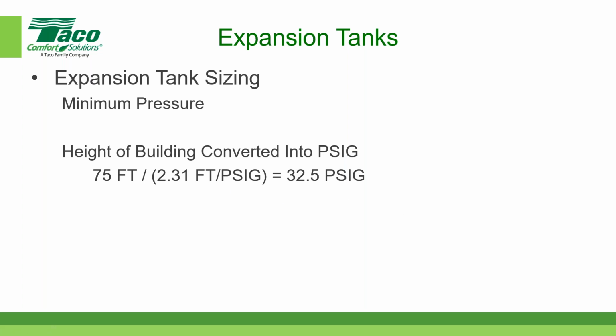The assumption here is that not only is our building 75 feet tall, but the piping system goes from the lowest part of the building to the highest part of the building. So if we want to determine what the pressure is at the bottom of the building, which in our case just happens to be where the expansion tank is located, then you would take that height and divide by 2.31 to convert that into 32.5 pounds per square inch gauge. So that's where you get the initial static pressure without any pressure at the top of the building.